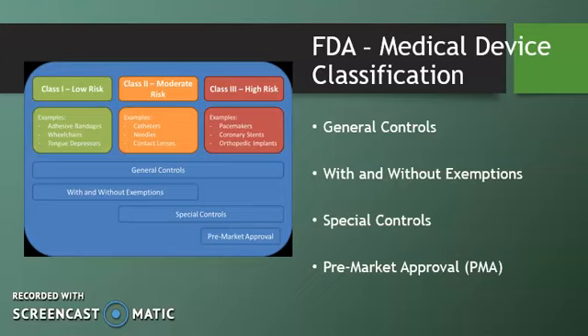Class 2 devices include devices such as sterilization equipment and biological and chemical indicators, considered to pose potential risks that require a higher level of regulation. Class 2 devices are subject to general controls and special controls. Class 3 devices include the most stringently regulated devices such as heart valves, pacemakers, and other life-sustaining devices. Class 3 devices are subject to general controls, special controls, and must obtain pre-market approval.